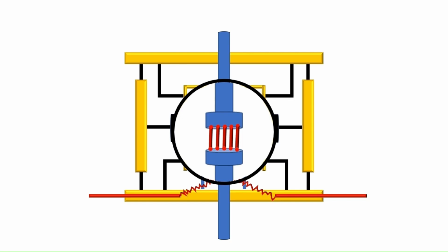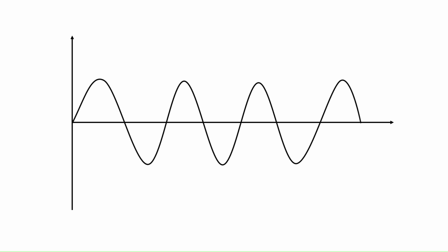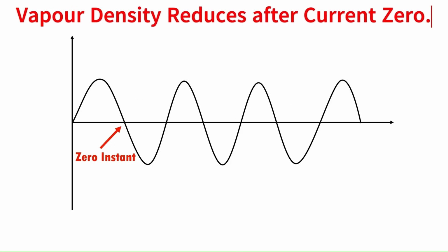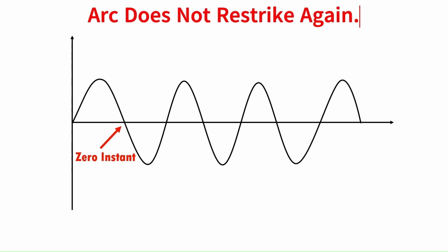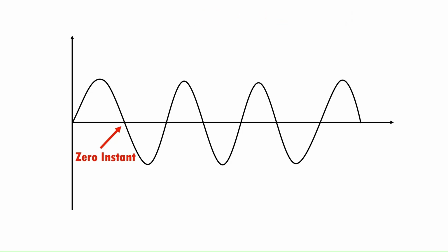This arc is essentially a plasma bridge that temporarily sustains current flow, even after the contacts have separated. The density of vapor depends on the current in the arcing. In alternating current waveform, at the time of decreasing mode of current wave, the rate of release of vapor also decreases. After the current zero, the medium regains its dielectric strength and vapor density around the contact reduces. Hence, the arc does not restrike again because the metal vapor is quickly removed from the contact zone.